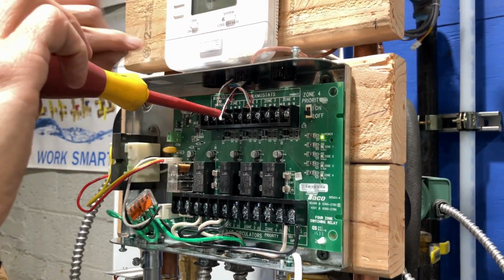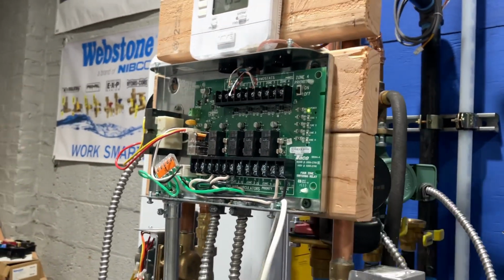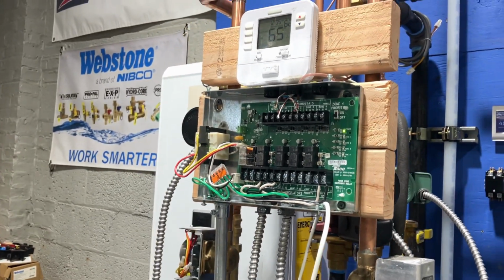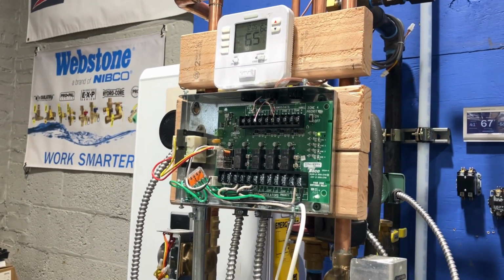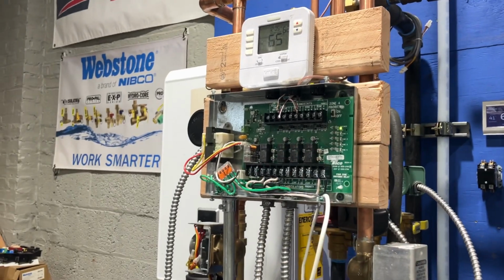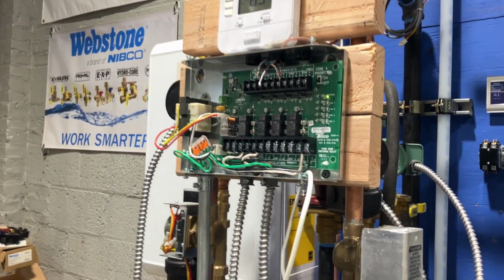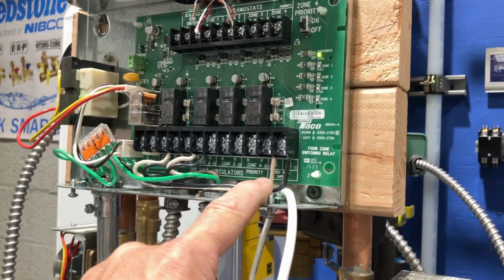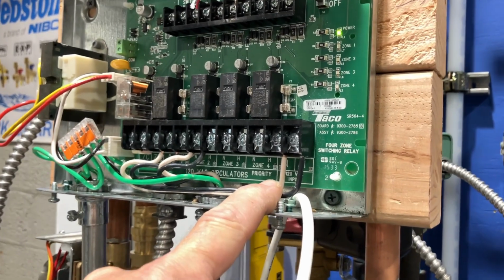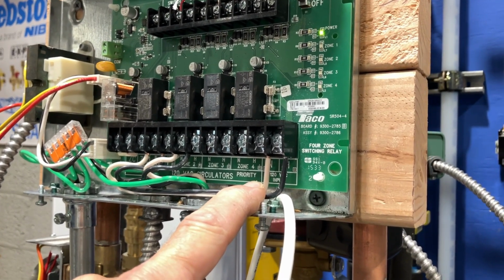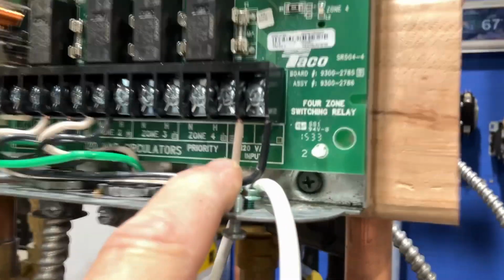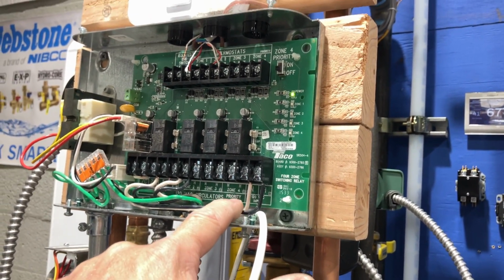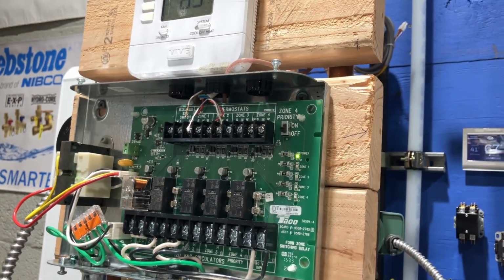Good. Now that's hanging out, so there is no active call right now. Right? Right. Okay. Let's talk about how this works. You ready? Okay. We have 110 volts coming in to the terminals marked 120 VAC or voltage AC input. Right there. If we have power here, that green light should be on. Should be is the key word.